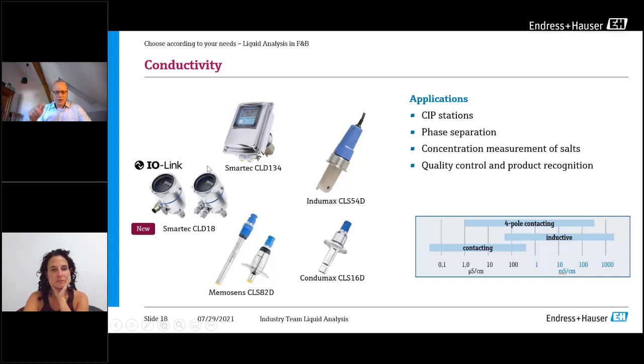Then, going down on the right side, we see the CLS16D, which is a 2-electrode sensor. It is very often used in water applications where you have to measure low values. Then we come to the 4-pole electrode sensors. This is contacting, and it is used if you want to measure a broad range, a little bit in the low range as well as at higher values, and in very small line sizes, because it has a 12mm design at the tip, so you can introduce it even in the smallest pipes.